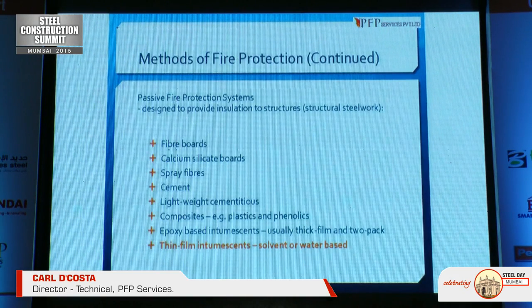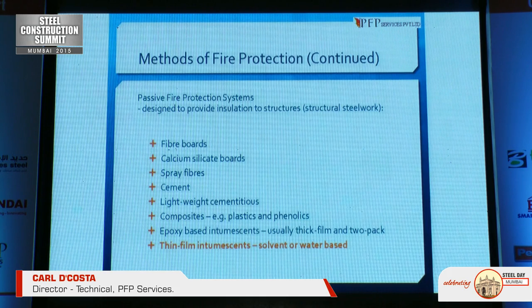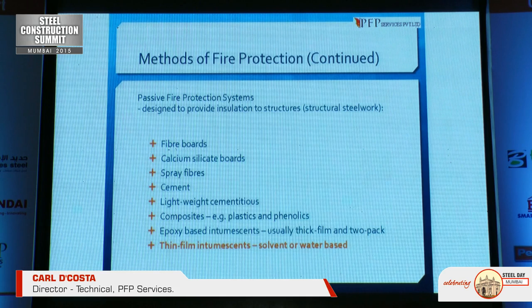And then there are passive systems, which are designed to provide insulation to the actual structure — the structural steel. Materials used include fiber boards, calcium silicate boards, spray fibers, cement, lightweight cementitious composites, plastics and phenolics, and epoxy-based intumescent — usually thick film, two-pack — which are normally used in hydrocarbon fire scenarios.